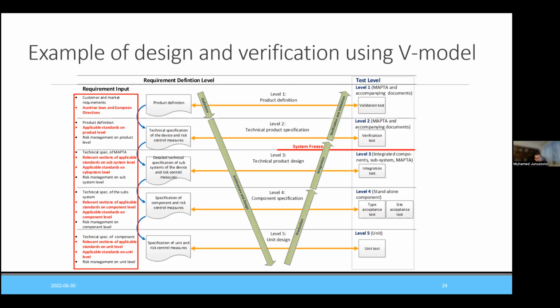First, verification tests are done against the technical specification of the device. And at the end, validation testing is done against the product definition and the user requirements. Once all testing is finished and everything has passed, the device can be used. Of course, before the use, the testing reports must be shown to the notified body, and after approval, the declaration of conformity is issued and the device can be used. It is much easier if the CE marking process is done in parallel to the design and development. Of course, it's possible to do CE marking on top of development, but the effort will be much higher.